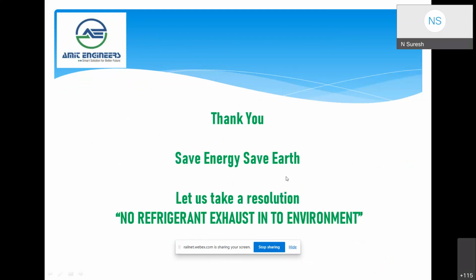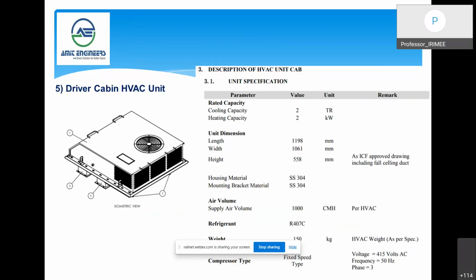Which refrigerant are we using? This is R407C, sir. Of the two compressors, the horizontal one is VVVF and the vertical one is fixed speed. No, sir, only one compressor is variable frequency. Initially it is only to pull down the temperature. For example, in hot summer the temperature will be high.